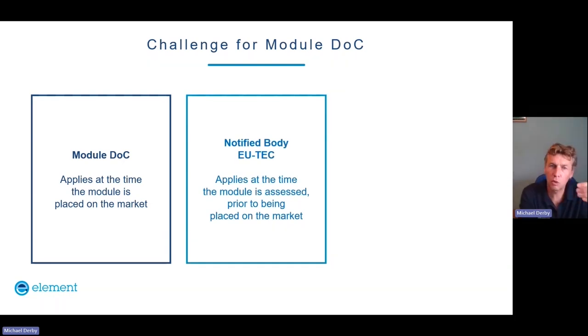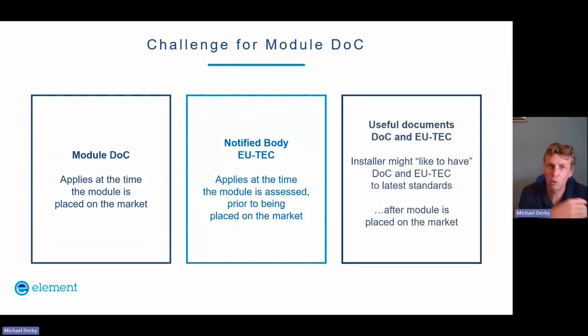But if you're selling modules of the same type or construction for years and the standard changes, new versions of the module will hit the market with different standards on its DOC. Your customer may not have used their first batch of modules, and they might wish their older modules had an updated DOC. There isn't really a process for updating a DOC of a product already placed on the market, because the DOC applies at the point of putting on the market. I think that's one of the main reasons why most module DOCs are online documents.